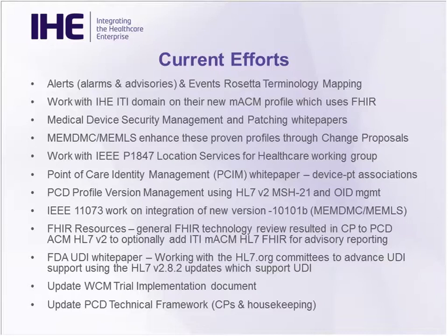So when FDA announced UDI, they didn't give a whole lot of detail in the communication from devices as to their identification. And they kind of left that to HL7. HL7 came over to PCD and said, when are you guys going to figure out what this is? So the PCD domain has been working with the HL7 Orders and Observations Working Group, of which a number of our members are members, to come up with updates to HL7 version 2. And as of 2.8.2, extensions have been added to support UDI.